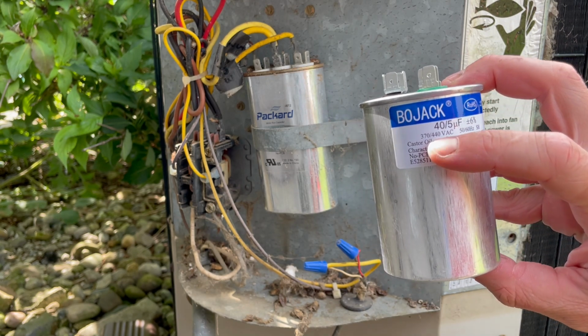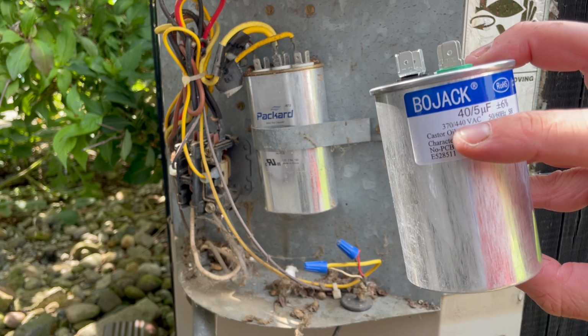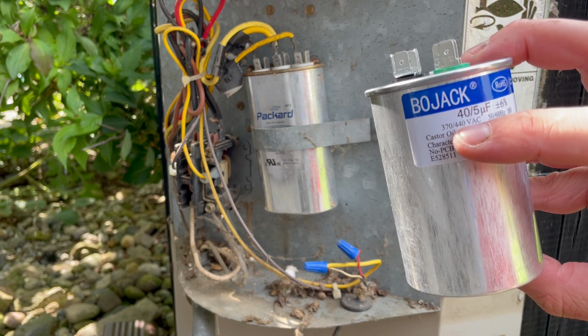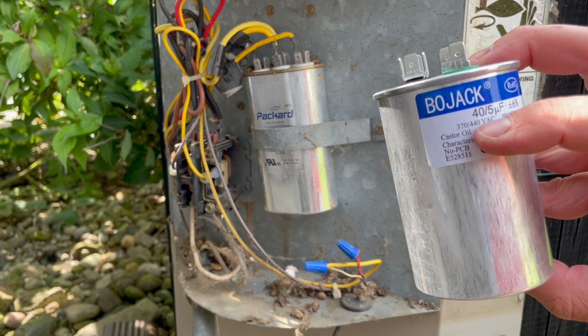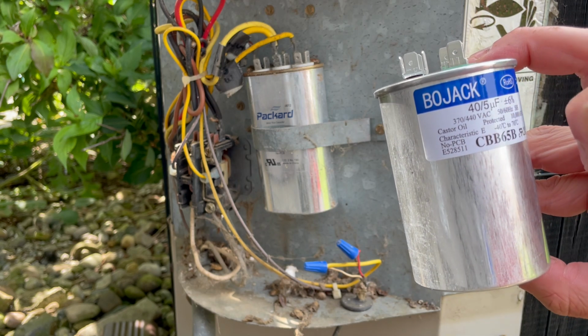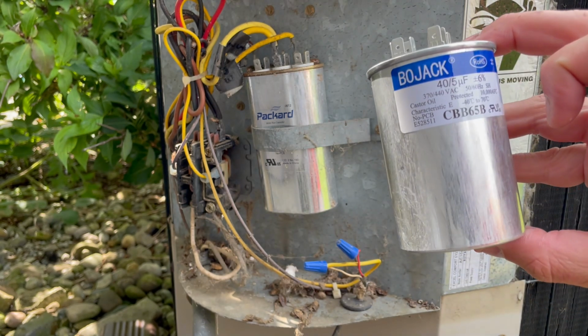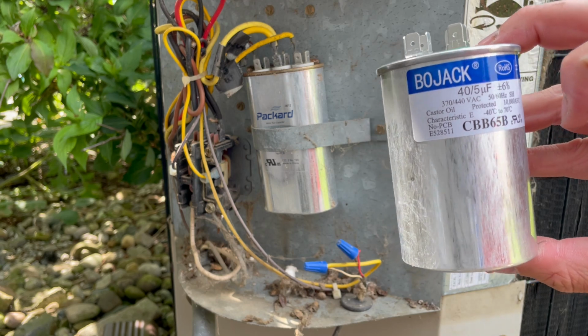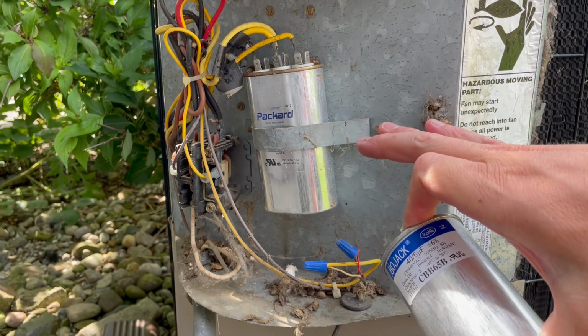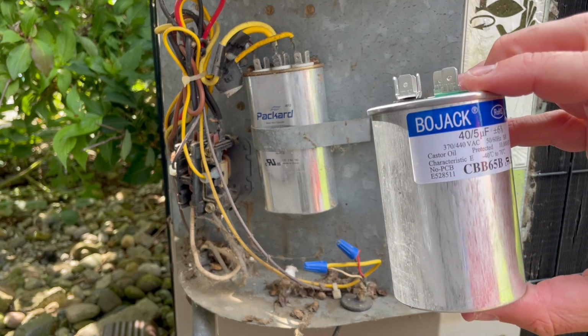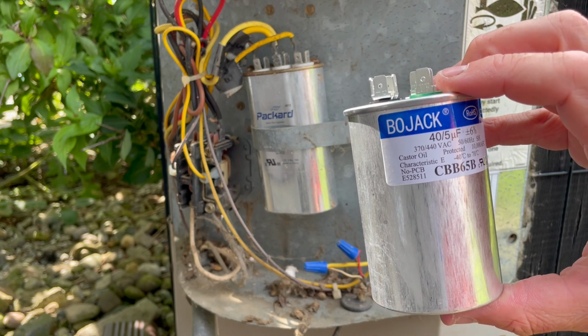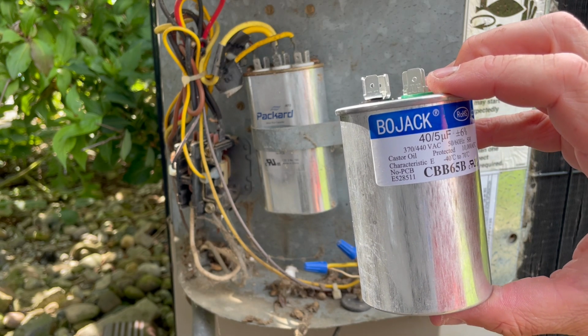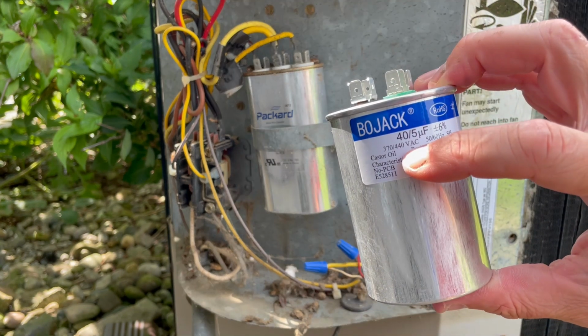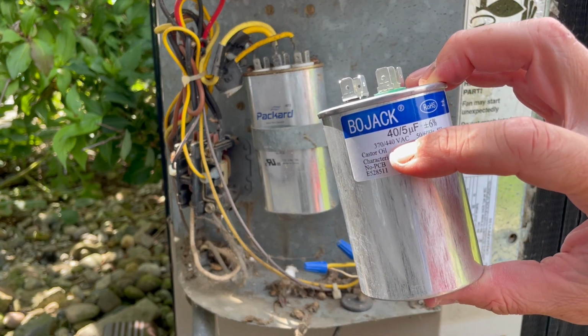The other important note is the voltage. In this case, it says 370 and 440. The 440 would indicate the maximum voltage it can handle. So even though our compressor is only 240 volt, when it starts up, you may have voltage spikes greater than what's actually being supplied. So it's important to match the voltage on your new one to whatever is installed.